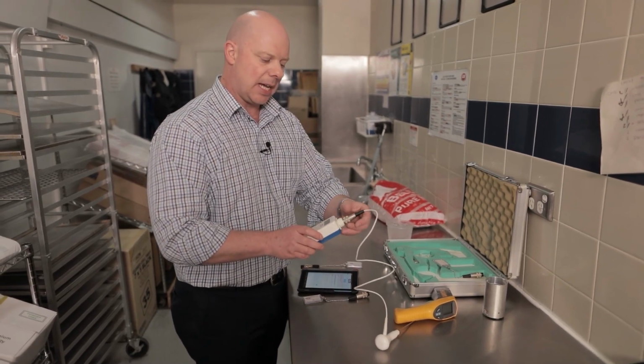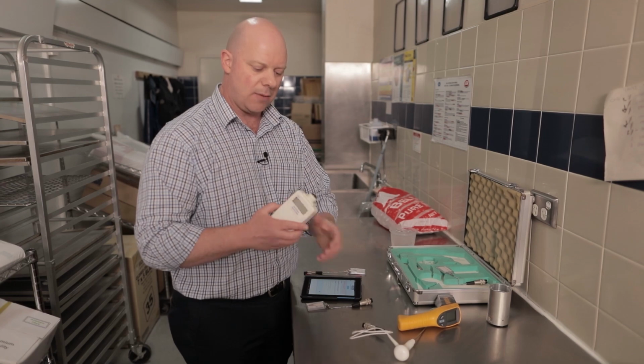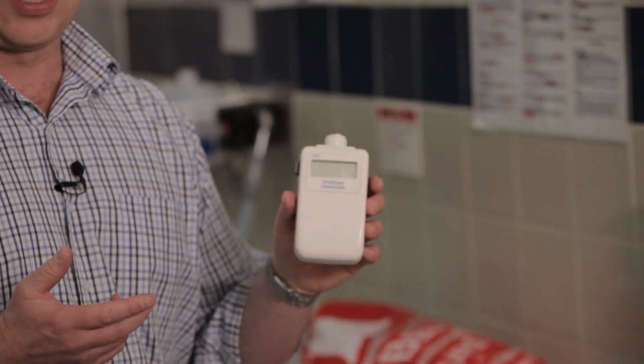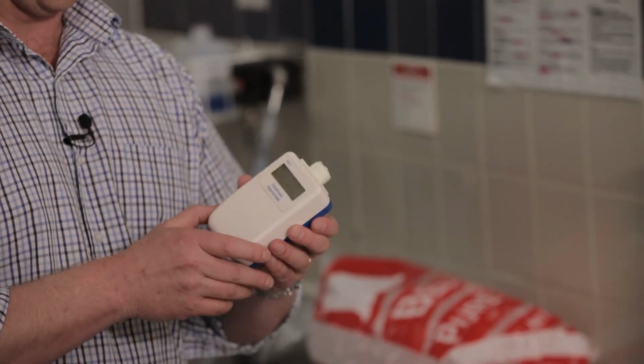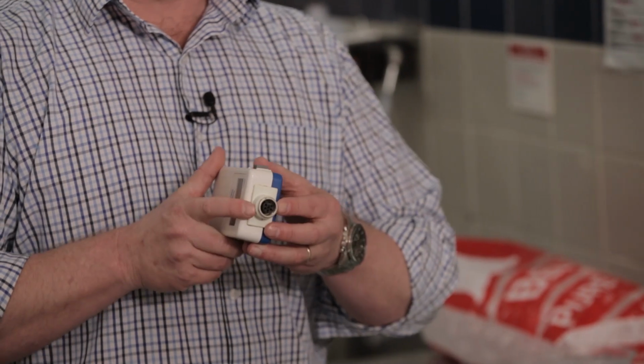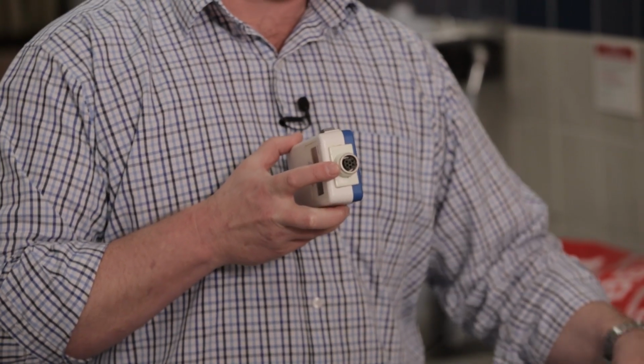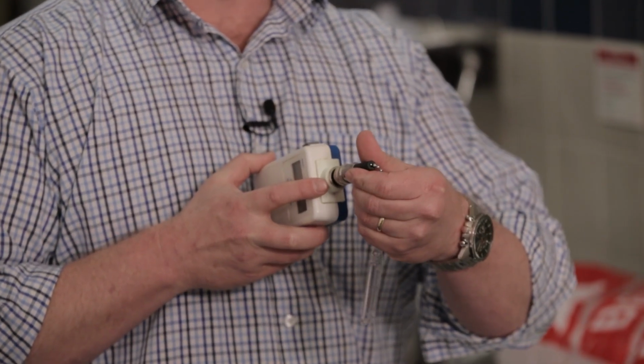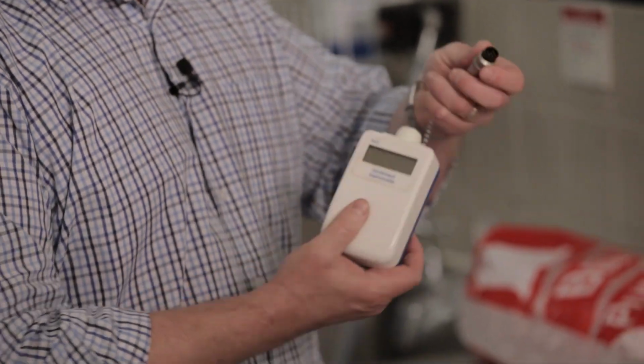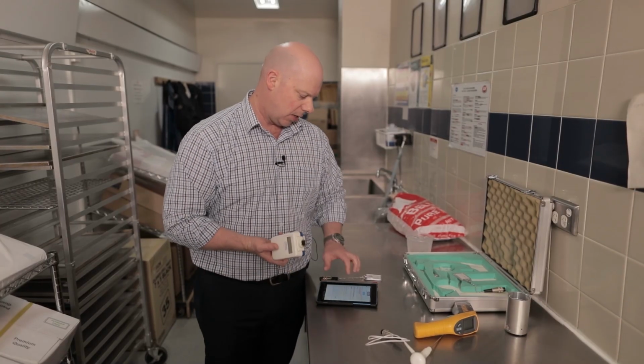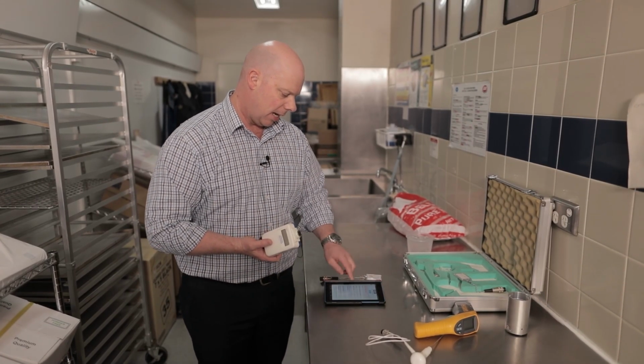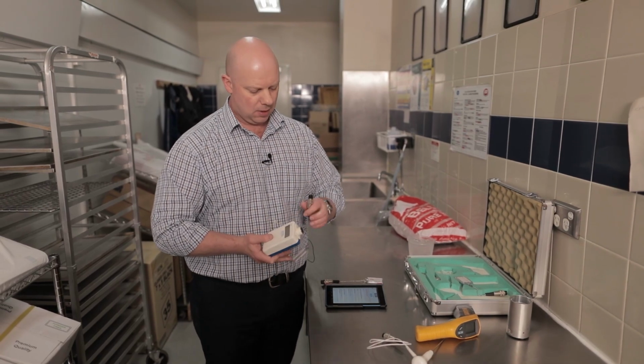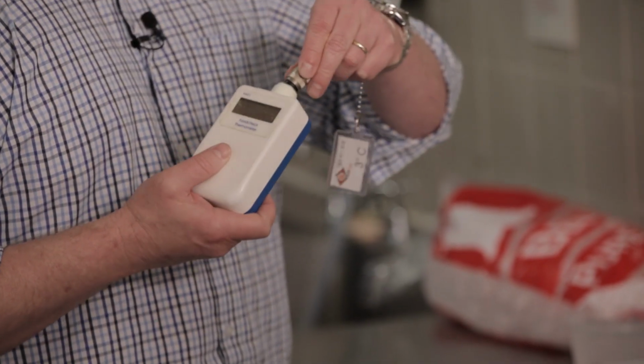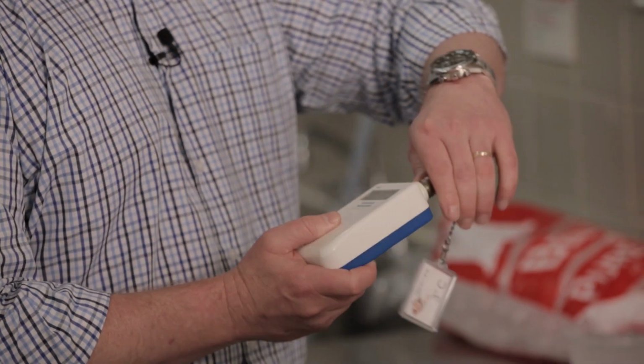To use these test tags, as I said earlier, you need to make sure that you've got one of these thermometers. Sometimes they look a little bit different. They may look a little bit newer, but at the end of the day, they're the only ones these test tags fit into the top with, okay? So the first check we're going to do, because this is the one that's on the log sheet, is the 3 degrees test piece.